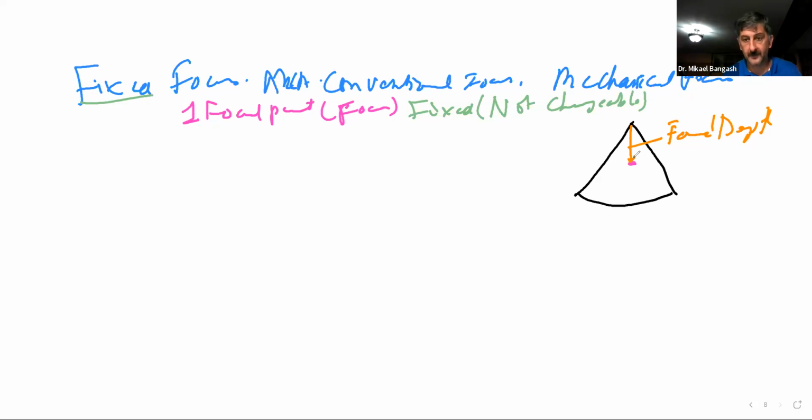Because if this depth here, in this case, was 2 centimeters, that would mean that in the entire span, 2 centimeters was the only depth at which this beam was going to be able to focus. This transducer is able to focus there because this is the point at which its beam would be at its narrowest. Although it's across this entire bed, how it goes from side to side is a different discussion. We will take that up in chapter 12.